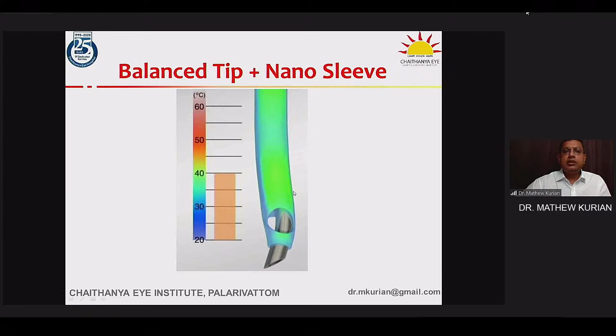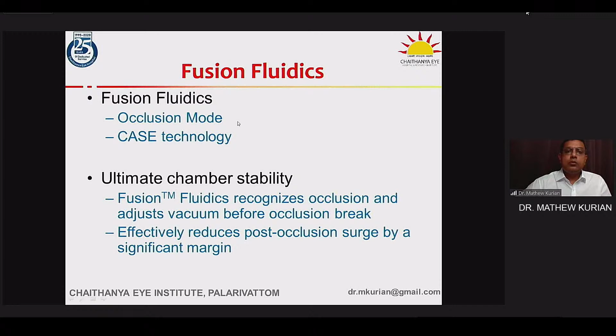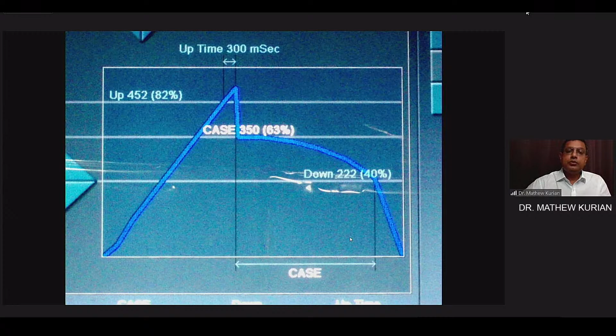Fusion fluidics on the Johnson & Johnson machine now has two components. One is the occlusion mode, where you can set independent fluid settings for unoccluded and occluded flow, and the other is CASE technology, where you can set the amount of vacuum rise and the duration for which the vacuum rise happens after recognizing occlusion. You can then step it down to what is considered a safer level, and then gradually bring it down to a more normal level as emulsification continues and chamber collapse doesn't happen.